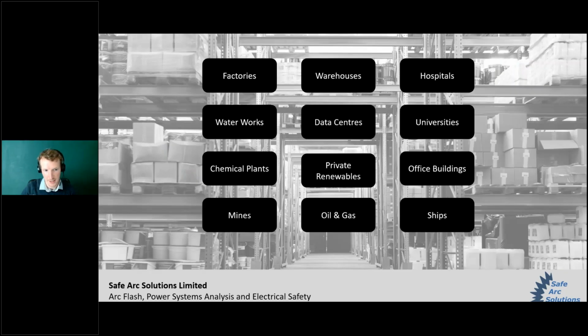So where can arc flash exist? Really, it's anywhere there are exposed, energized electrical conductors. In the domestic setting in our houses, conductors are rarely exposed — there's a lot of insulation and safety requirements — but laboratory tests have shown that arcs can be sustained with voltages as low as 208 volts AC. Still, it's much less likely to occur here than in commercial or industrial settings, where you've got 3-phase circuits, higher voltages, and more current. So that's where we tend to focus more of the arc flash efforts.